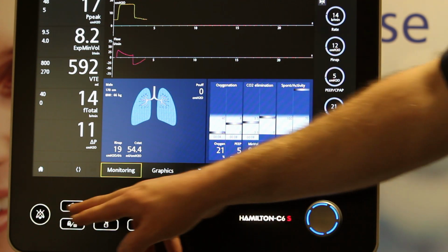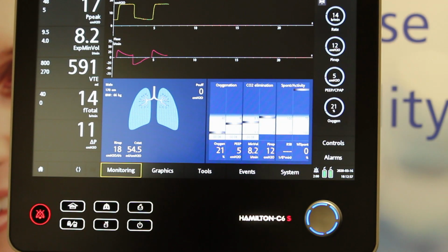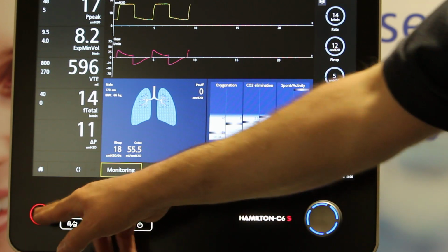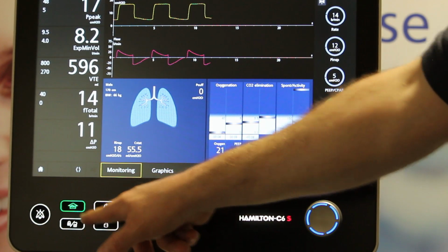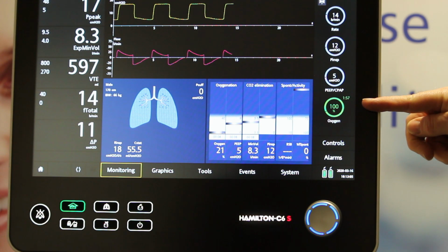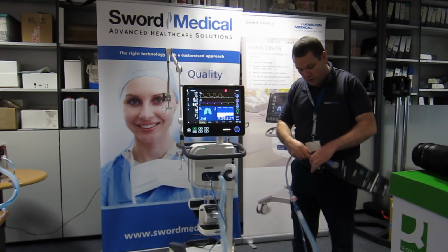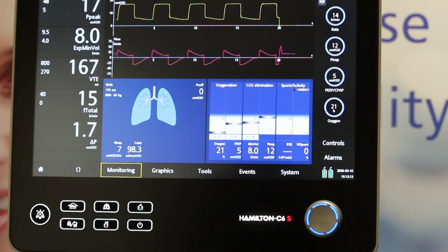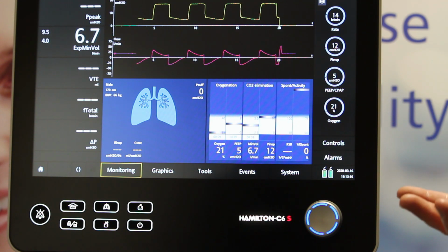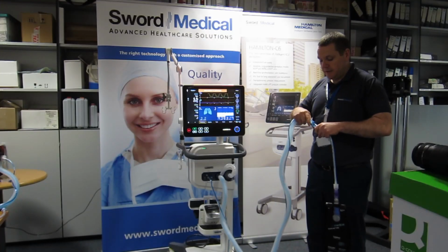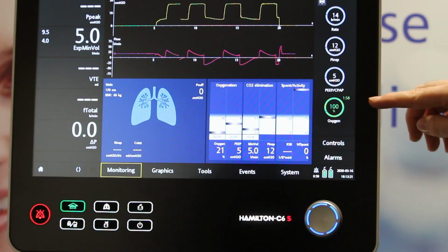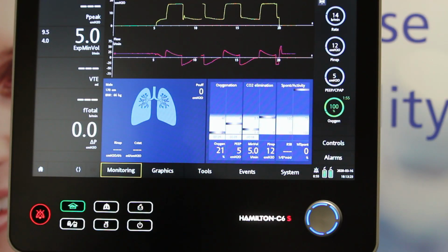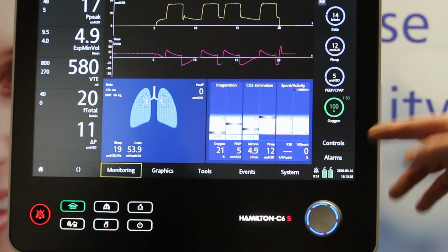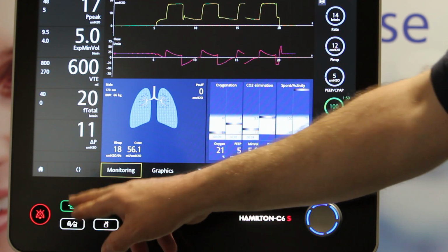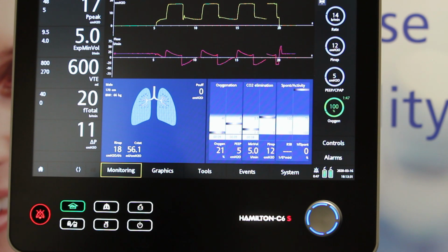And here on the hard keys then we've got our alarm silence button. It silences the alarm for 2 minutes unless you get a fresh alarm. Then we've got our O2 flush, so when I press my O2 flush it gives me 100% oxygen for 2 minutes. If I'm doing open suctioning, then when I disconnect from the patient, the ventilator will give me a minute unalarmed to do my suctioning manoeuvre, and then when I reconnect it'll automatically start to ventilate again and gives me 2 minutes of 100% oxygen for reoxygenation. If you're doing closed suctioning, you just press your O2 button and you will get your 2 minutes for your closed suctioning manoeuvre.